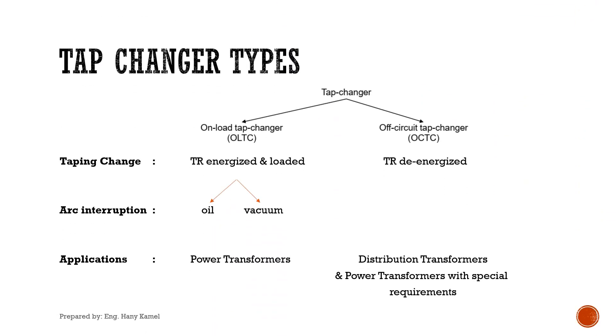Tap changer types. We can classify tap changers from an operation point of view into two different types: on-load tap changer and off-circuit tap changer. With the on-load tap changer, the tap changing can be done with the transformer energized and loaded, as it is provided with arc interrupting facility.